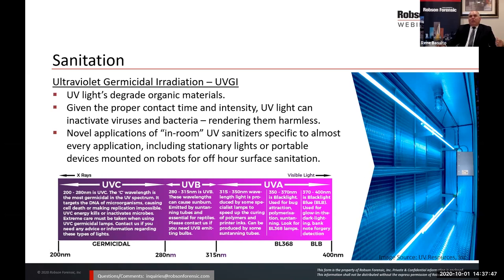It's nothing new. The most common application we had for these lights before, since they kill and inactivate bacteria and viruses, was to keep the coils clean, to prevent any bacteria growth within the coil and within the drain pan, to keep the drain pans clean, etc. However, since this has been known to be so effective, the biggest use now has been for sanitation of the airstream itself. It's almost like a byproduct of the process, but the demand is out there. You'll also see, I haven't been seeing them lately, but when the whole pandemic started, you would see robots going into hospital rooms and turning on the UV lights. And I saw one where they were walking a UV light generator down the aisle of an airplane and they were irradiating all the seats in the airplane. So it's a very effective solution.